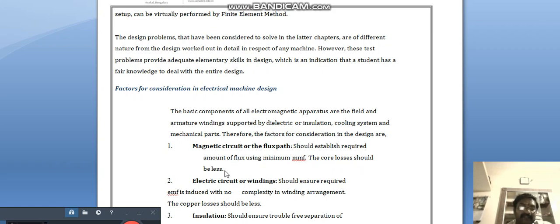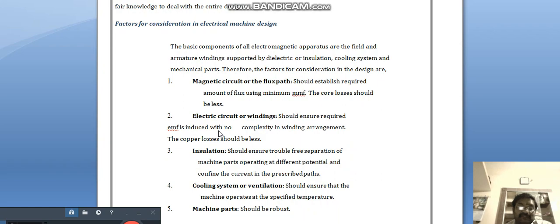The electric circuit or windings should ensure the required EMF is induced with no complexity in winding arrangement — the arrangement should be easy while producing the required voltage. Insulation should ensure trouble-free separation of machine parts operating at different potentials and confine the currents to the prescribed path only, since improper insulation causes current to take a lower resistance path.